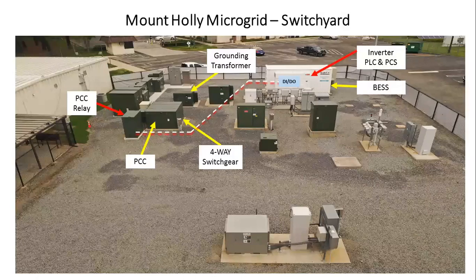There's an AC coupled battery, which is the battery energy storage system that consists of the inverter and the battery. There is a connection between the PCC relay and the battery energy storage system. There's this line that says DIDO, which is probably the most critical part for ensuring the seamless transition. So that is inside the microgrid yard.